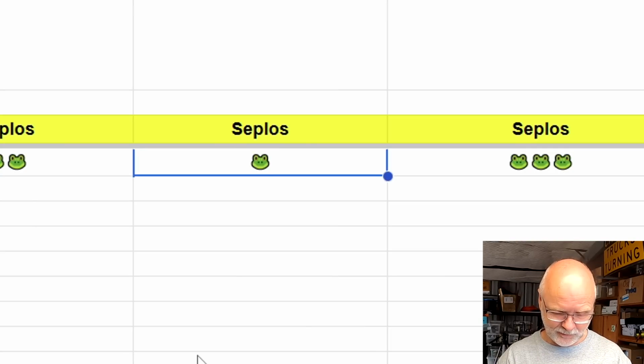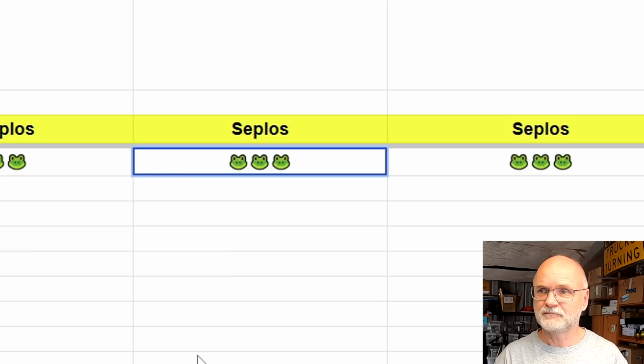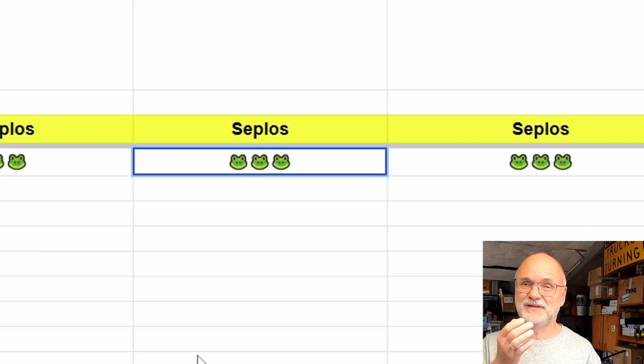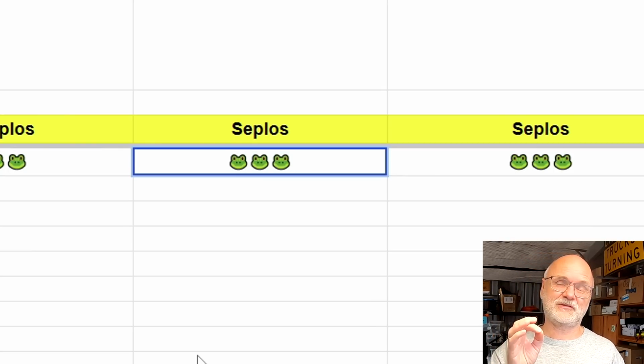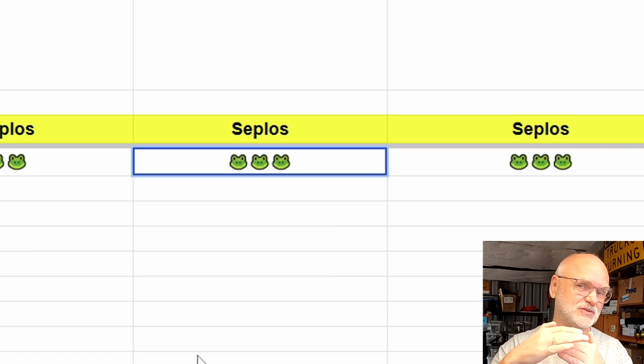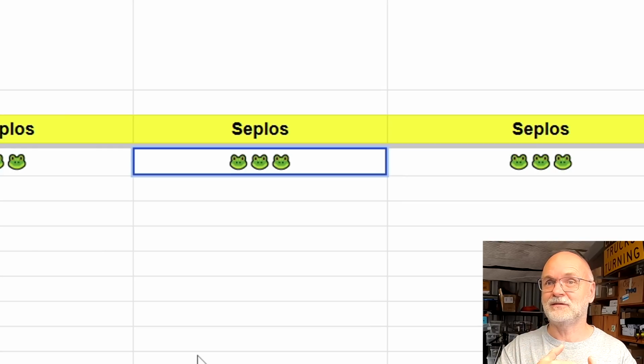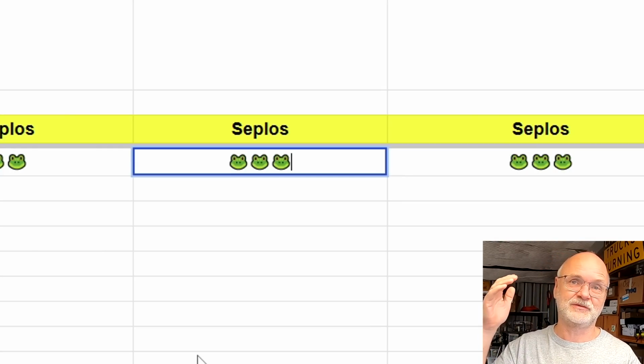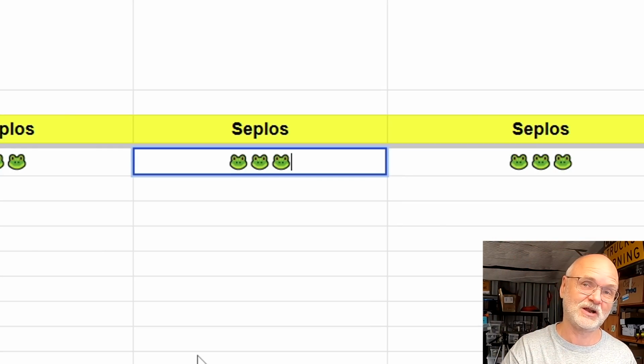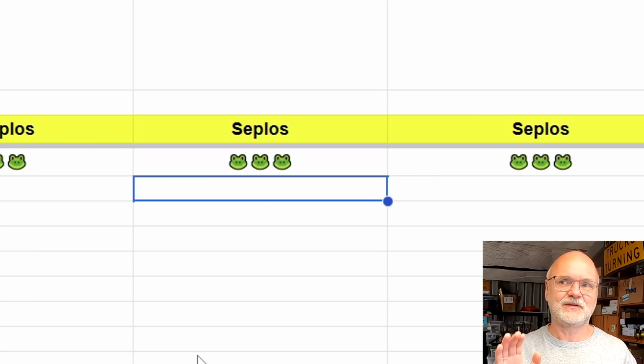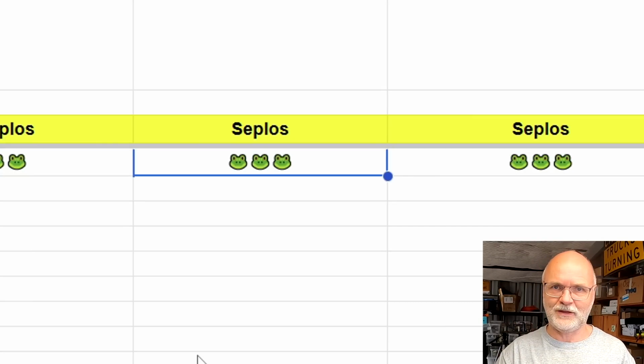Okay, then the only thing we need to do is here give this BMS more than one frog now. I would give it, is there anything which is not working now anymore? Well, the limitation here is now that it only works like this with a Victron system. Because now we can go into the DVCC and set a maximum charge voltage limit, which is independent from the over voltage protection the BMS tells your charger to charge to. So in this case, I would leave it in three frogs from 1 to 3.